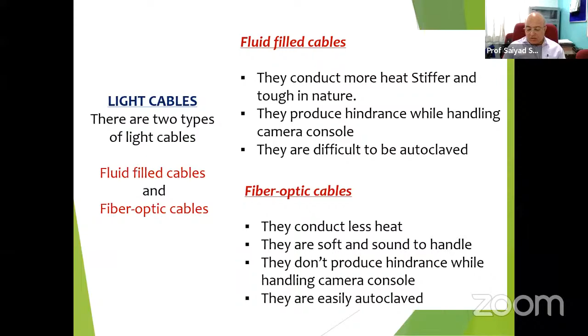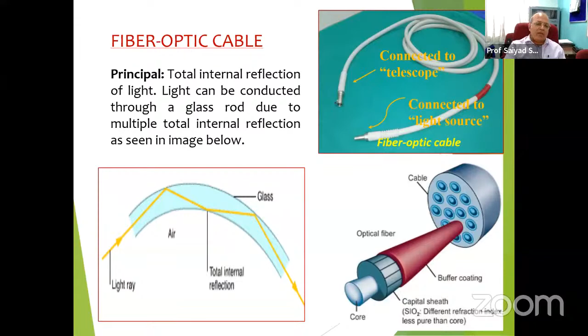They are difficult to autoclave. Now the fiber optic cables conduct less heat. They are soft and sound to handle. They don't produce hindrance while handling the camera console. They are easily autoclaved. That is why you see the fiber optic cable having 2 ends, one end connected to the telescope and the other end connected to the light source. You see one fiber of the fiber optic cable, and how the light travels in the glass and the air and the light rays.